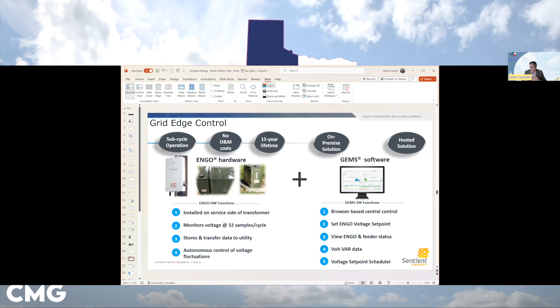This is a really messy graph, but it's easy to talk to, and for me it's kind of intuitive. On the left, you see normal operation - we're looking at the voltage on the secondary side of the transformer. You see the voltage itself fluctuates quite a bit between the lower and upper ANSI limit. That means on the primary side, your voltage has to be really high to keep it above 114 volts. Now, with our deployment of the device, we're able to optimize the voltage.